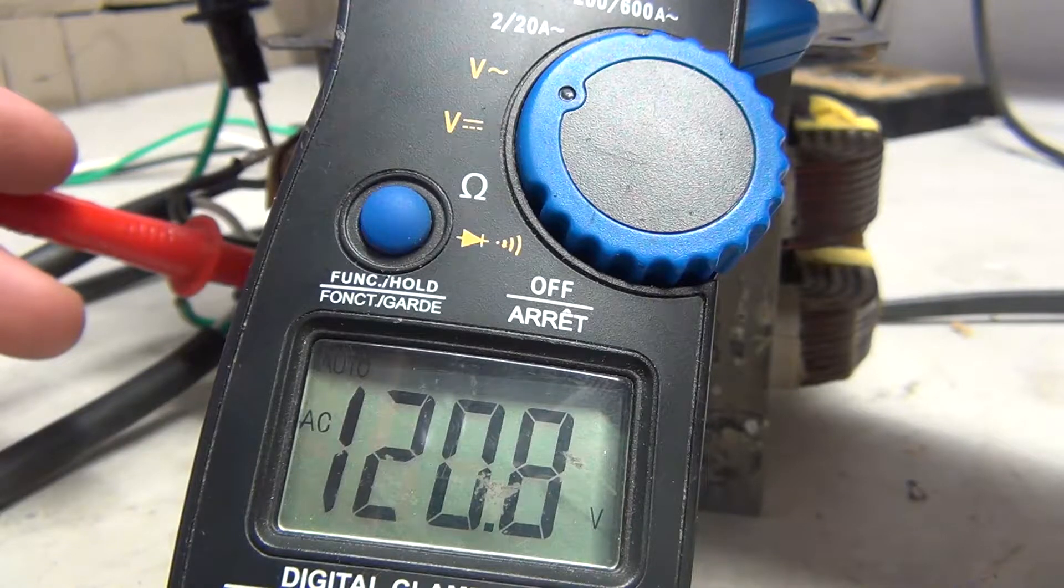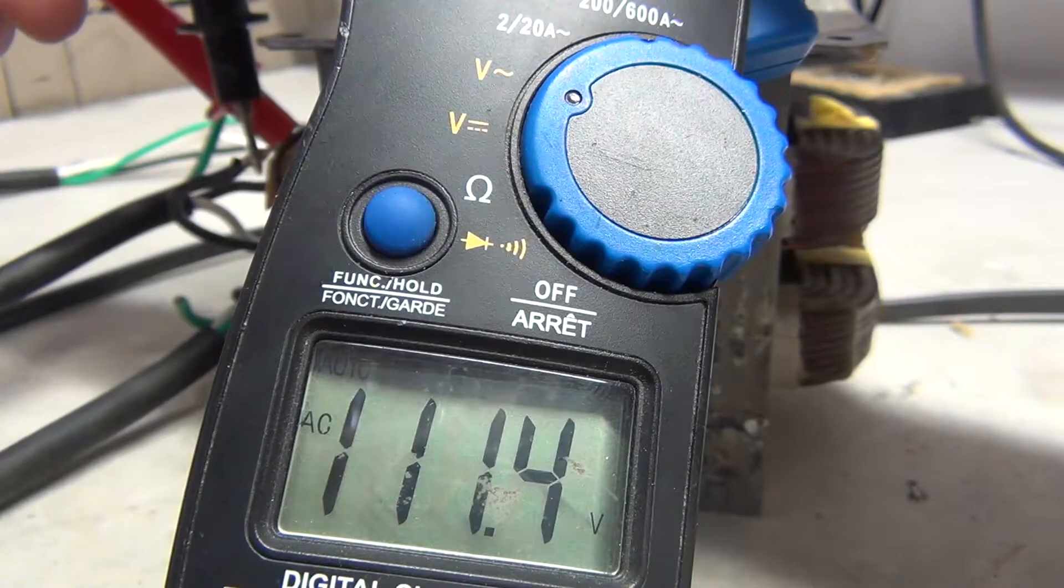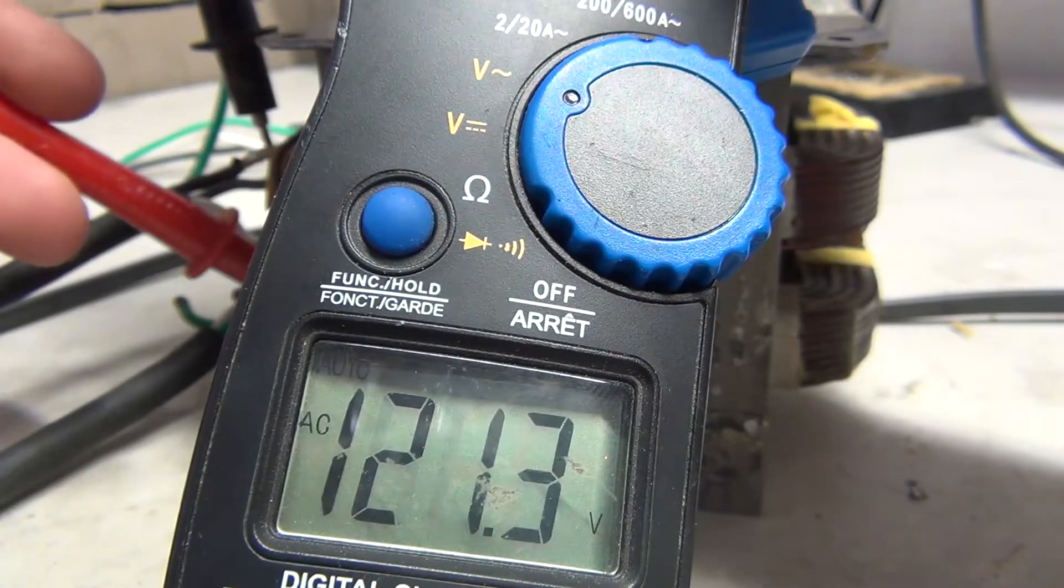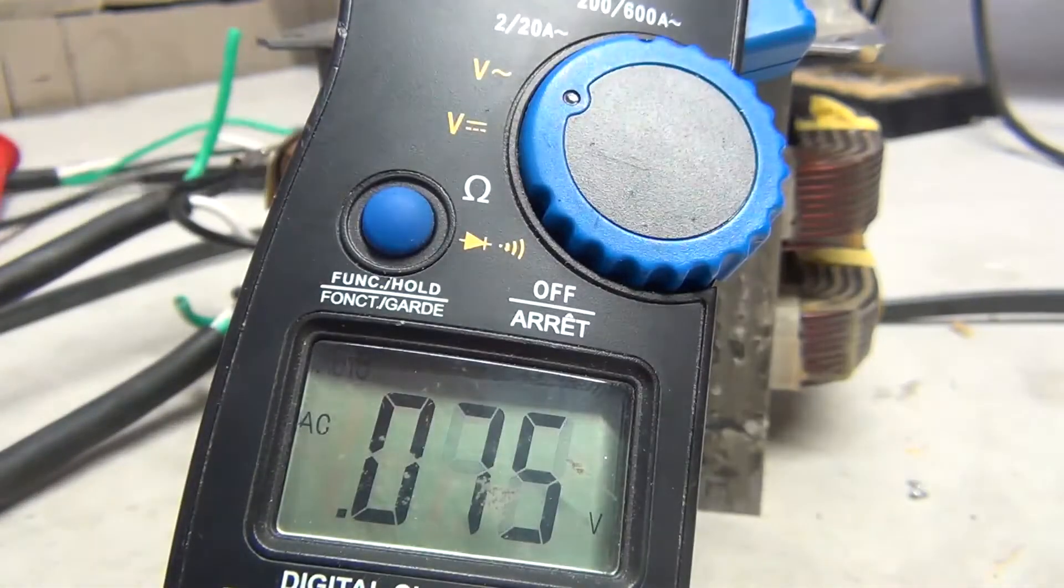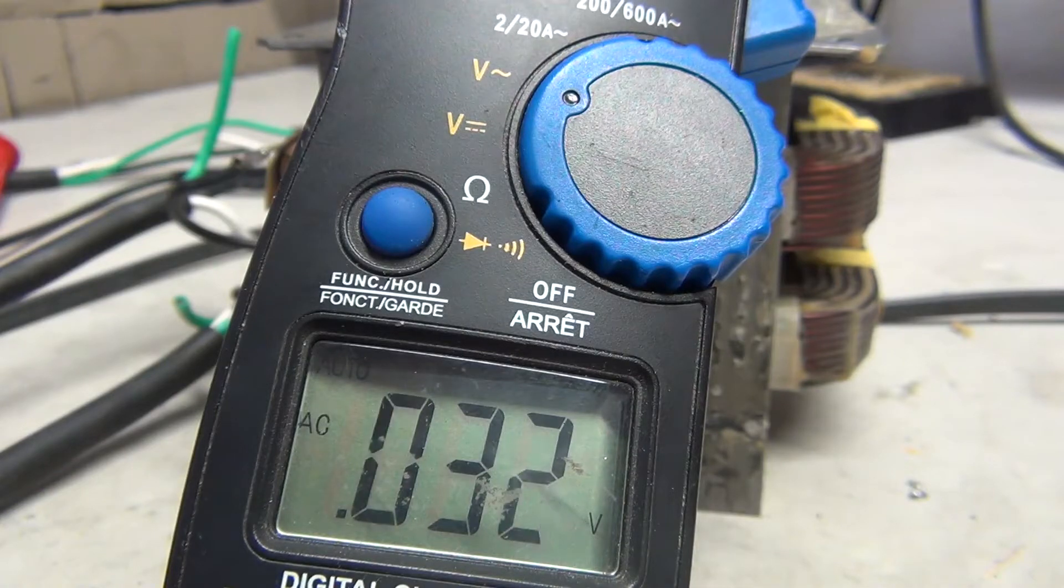And then line to neutral for the first one is 120. And line to neutral for the second one is 111. So you got a bit of loss there from different winding counts, but it's close enough to be usable for just a rigged up system.